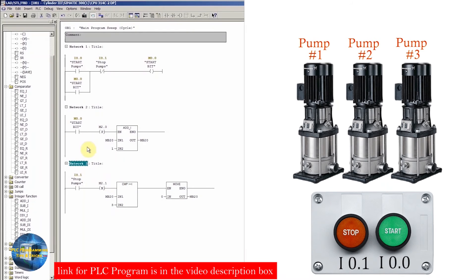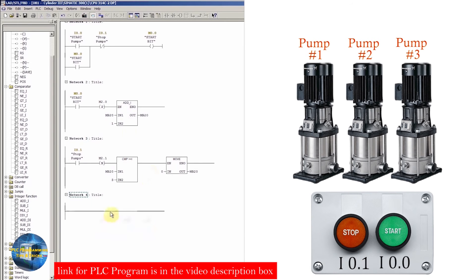So up till now we have written logic that creates a counter. The first time we turn on the start bit, MB20 equals 1. The second time, MB20 equals 2. The third time, MB20 equals 3. Whenever the value reaches 3 and we press the stop push button, the negative edge will reset MB20 to 0. In the next network, we will use this MB20 value to turn on the pumps and change their duty cycles.